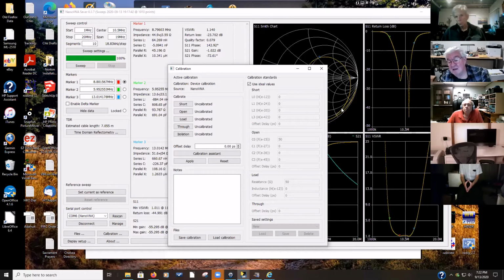In these VNAs, the default is the opposite, where you have 5 memory locations, for example, and location 0 is the default calibration. And each time you come in, it automatically goes to that. And for new guys, that saves you having to calibrate so much. But if you want to change things, this goes from 0 to 1,000, say, from like 10 kilohertz to 1 gigahertz is the typical range. And a lot of them suggest that you calibrate it for that entire range. But if you're an HF person and you want to look at a filter at 10 megahertz, the other 990 megahertz is not of a great deal of interest. And so what you can do is enter on the screen here in the upper left corner the areas that you're interested in.